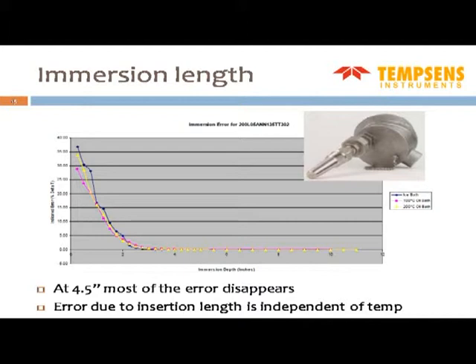So for a 12 millimeter tip, you can see that if we are not inserting more than 10 times the diameter, you are going to have a lot of error. It's the error in percentage, and if the insertion is not proper, then we will have a lot of error in the reading. So immersion, as Mr. Clem told, should be about 10 times the diameter of the tip. Plus you have to add, in the case of an RTD, another 20 to 25 millimeters for the sensor length. Only then can you get the proper temperature accuracy.